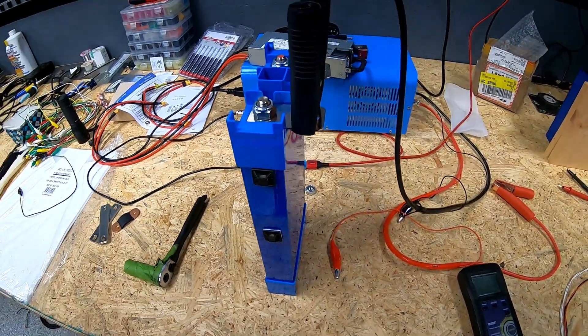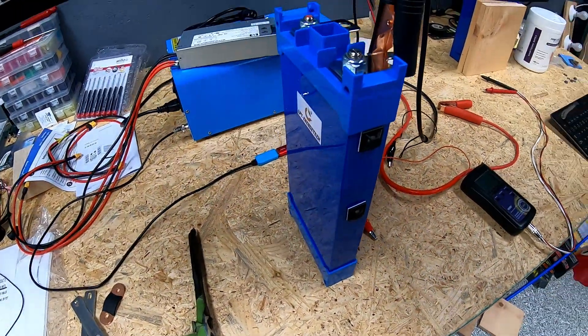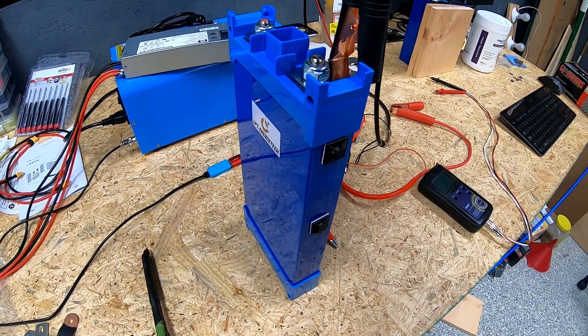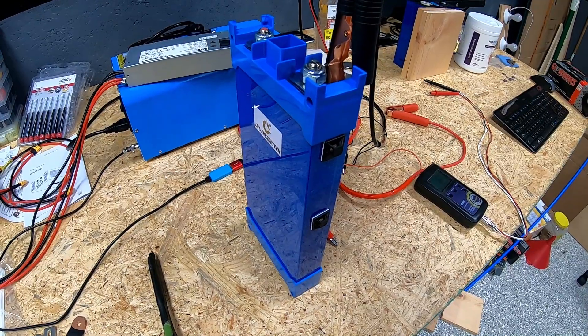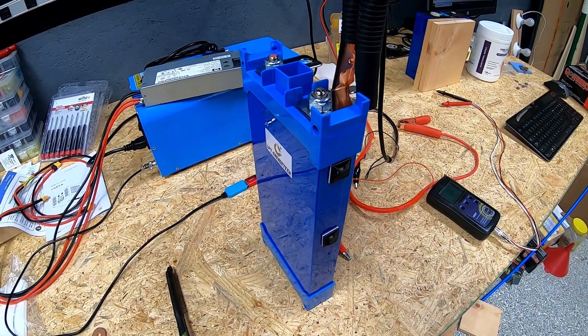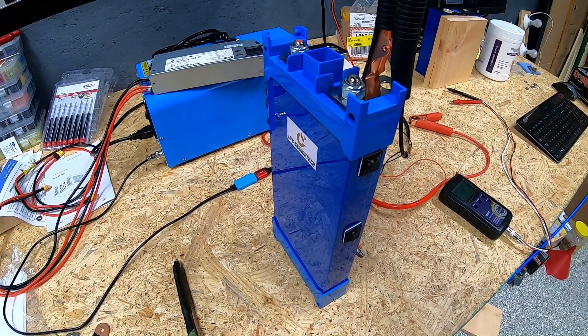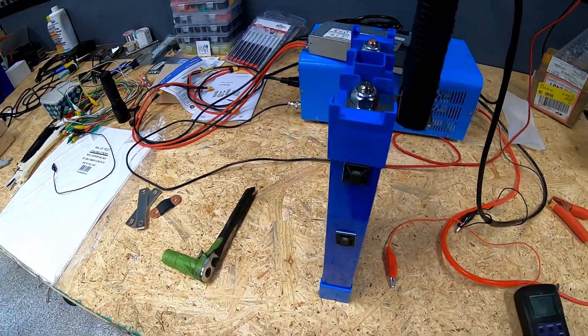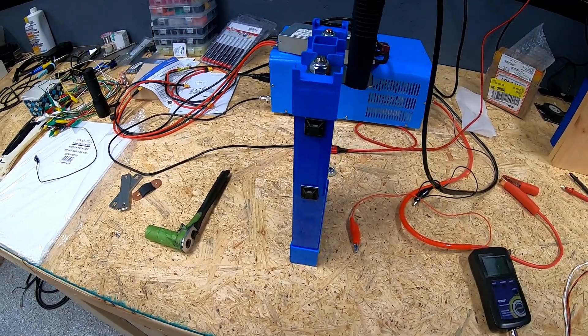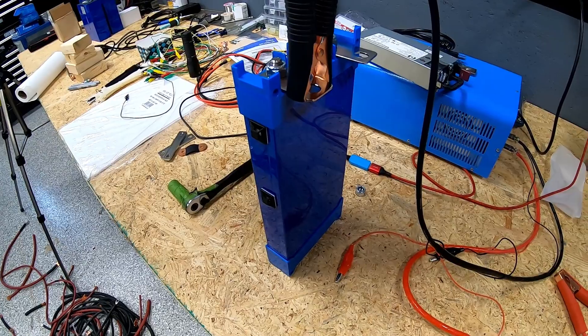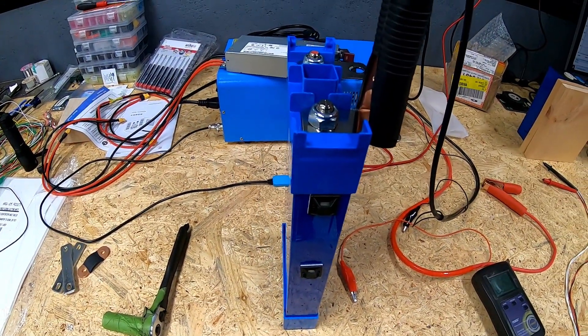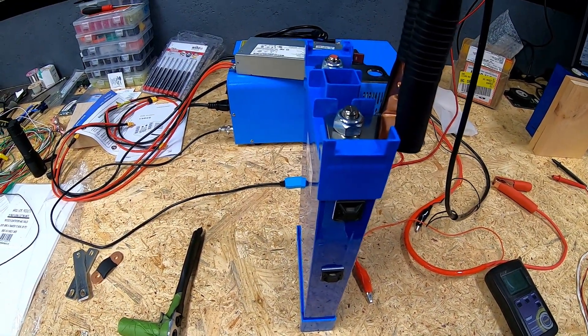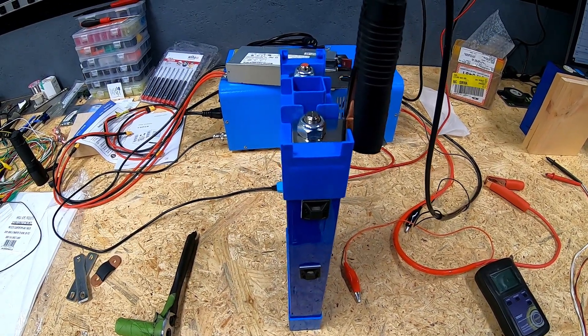We didn't want to store them at their 100% capacity. These cells, at least what is stipulated by the manufacturer, if you're going to store them for a while, they suggest that you don't store them at a fairly high state of charge. So again, two reasons: one to eliminate the possibility of having issues when we were doing the decommission, and two because we were going to store these for a bit.